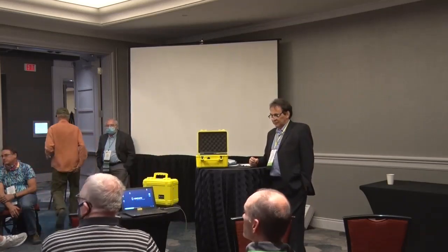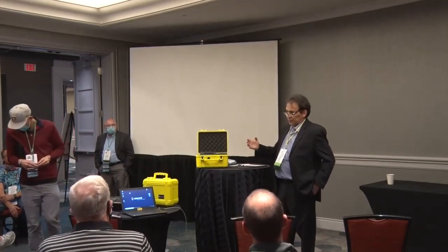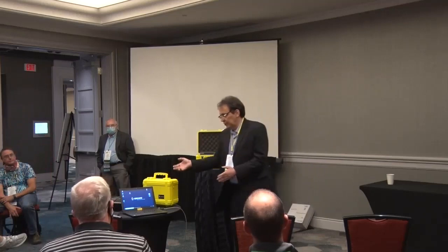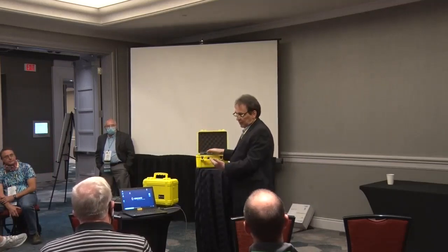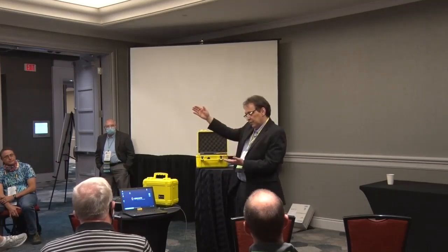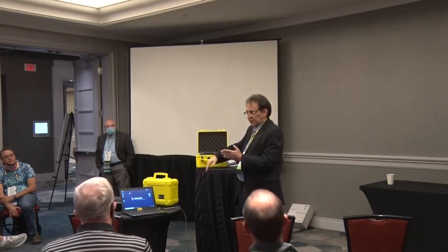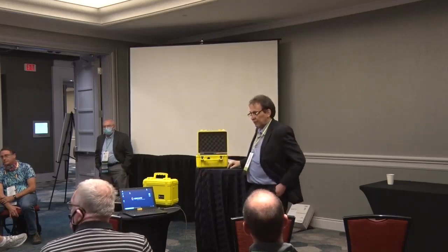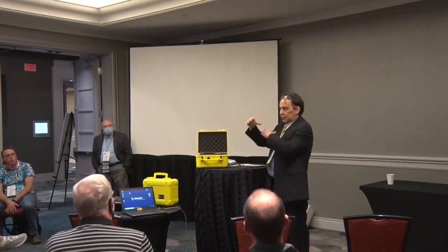Does this discriminate between the thoron and the radon? It has a sequence. It'll tell you, okay, put it in the source, it'll fill it for 90 seconds, and it'll stop pumping, and it'll see, do my counts go up? That means you're measuring radon. Or do my counts go down over the next 3 minutes or 5 minutes? If I have a questionable reading, I can go to that thoron function. That's good. Then it does a mathematical regression and gives you a percentage between the two.